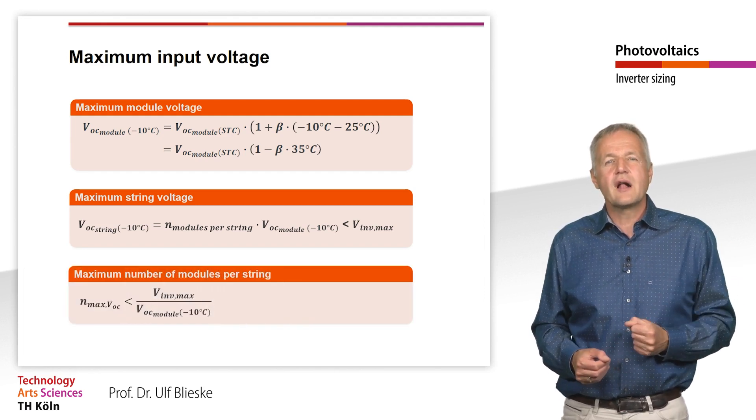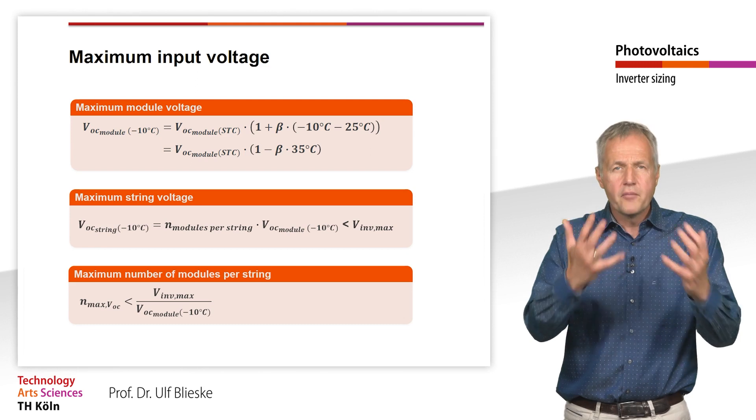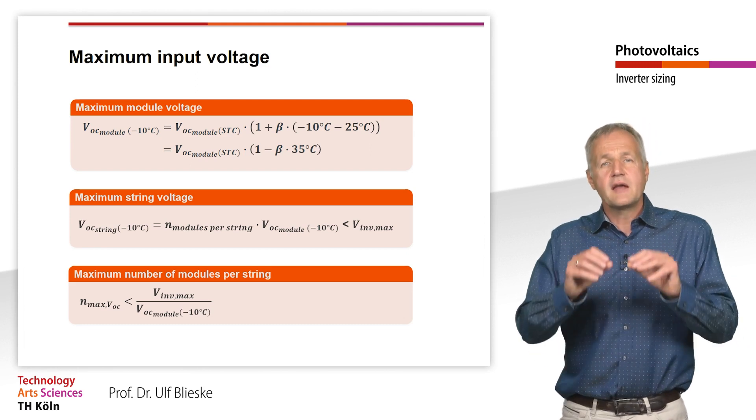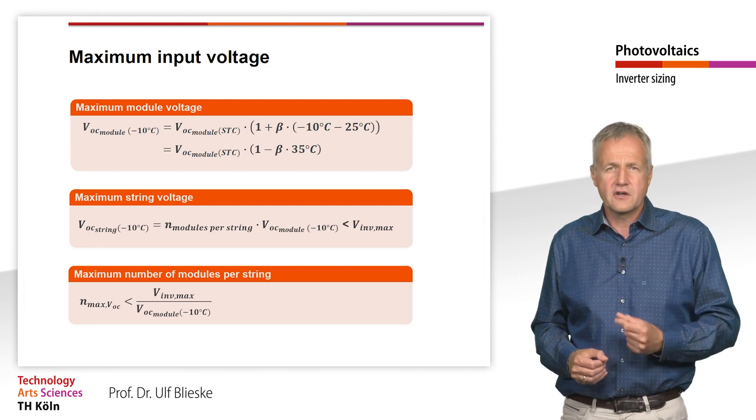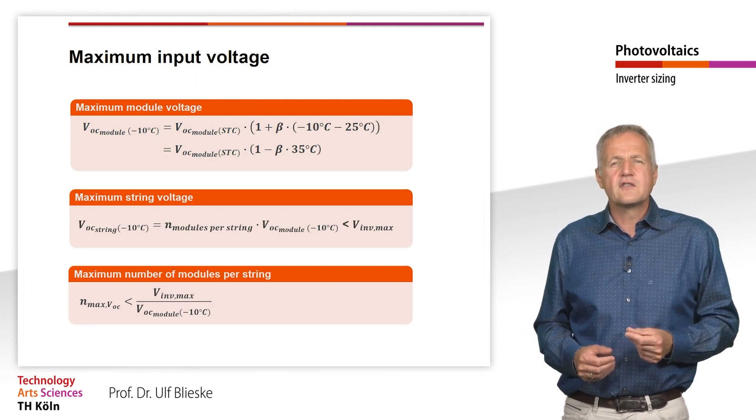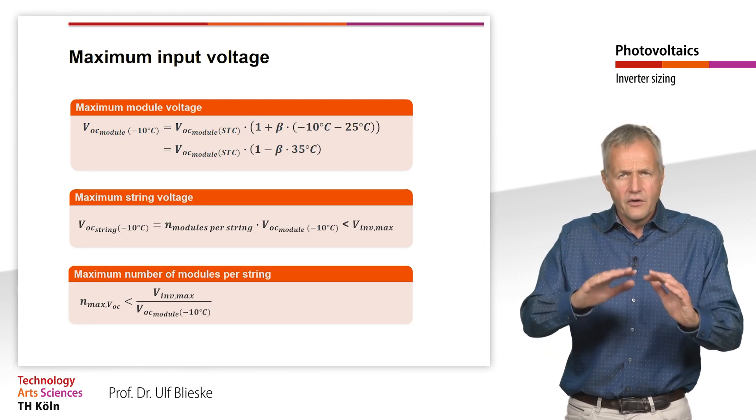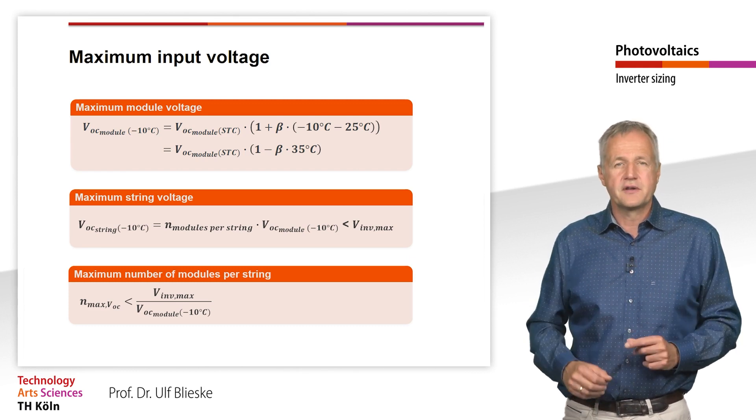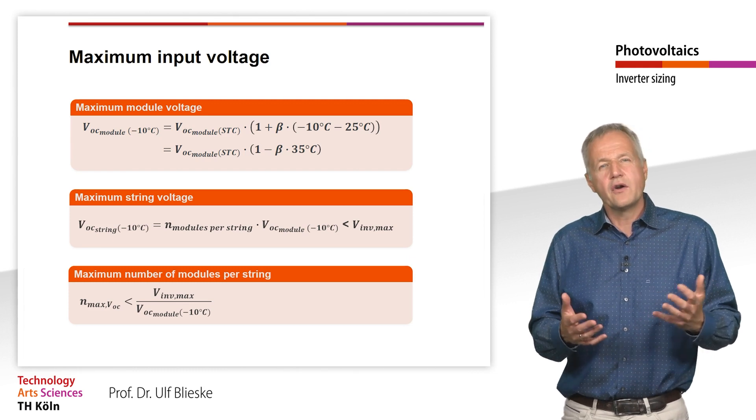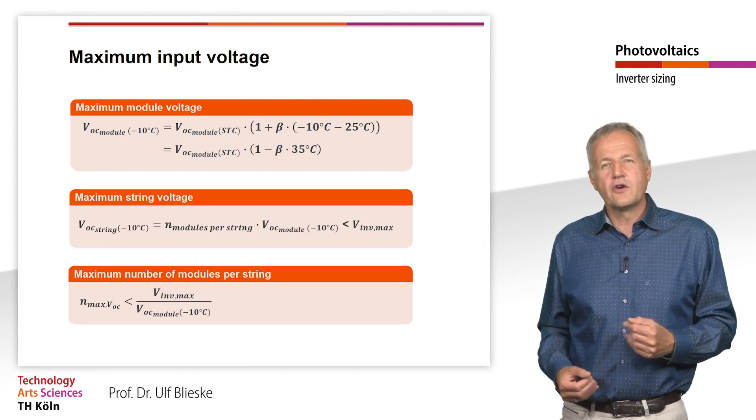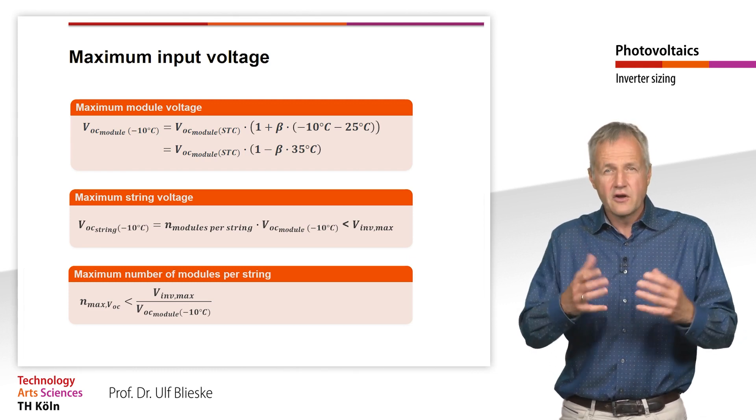Conversely, we can also calculate the maximum allowed number of modules that then can be connected together in a string for a particular inverter. This value is of course always rounded down to the nearest whole number. It may then be necessary to leave out one or even more modules in order to be able to use a particular inverter.